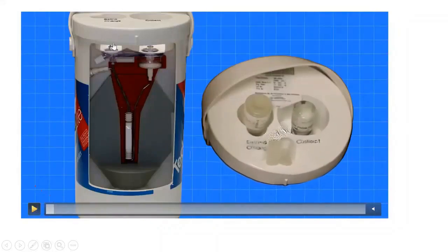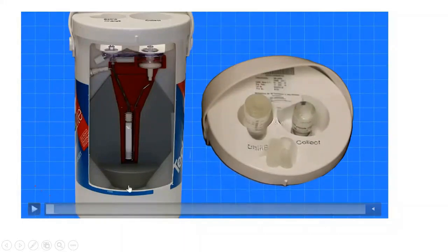Here we have a second tube and a second shield. The white part is molybdenum, which is located in this section. Of course, the part you see is filled with lead to prevent any radiation from escaping outside the generator. This is the shape of the cover. On top of the cover, there is an opening and a needle where we place saline. And there is another opening where we put it to collect the radioactive material.